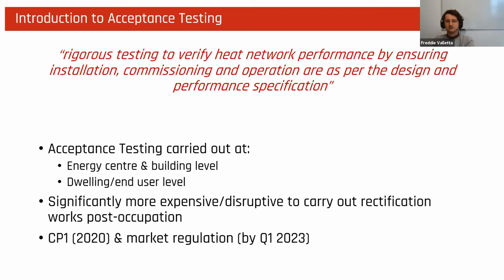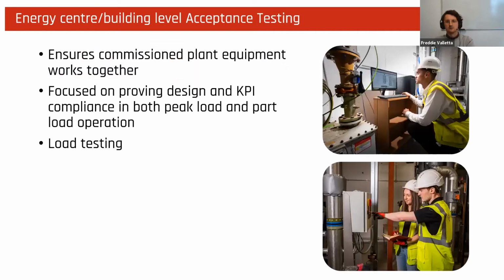So now we'll detail the two types of acceptance testing, starting with the energy center and building level. As I said, at the building level, there's been a historic focus on commissioning your individual components separately, with the assumption that the control system will tie all of the operation together, with occasional tests proving that the system can actually operate stably at its peak load. However, as heat networks are dynamic systems, the plant equipment needs to be proven to operate under variable and part loads, seeing as these peak loads are rarely seen on systems and only last for a matter of minutes.